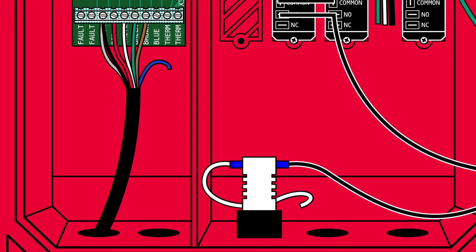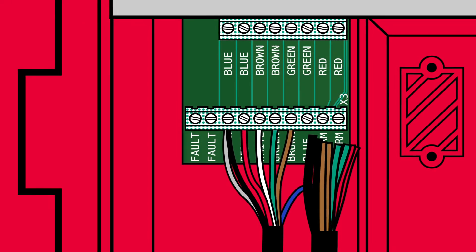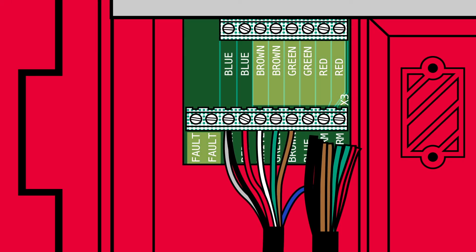The connections for the remote fire panel use normally open relays that close when the switch is activated. These connections come into the low-voltage area and connect to the top terminal block with two positions in the lower terminal. These will indicate the state of the water level control switch points, including a power loss instance.